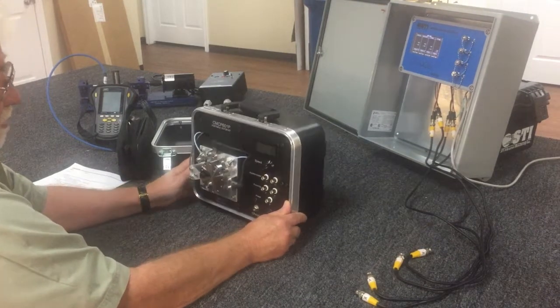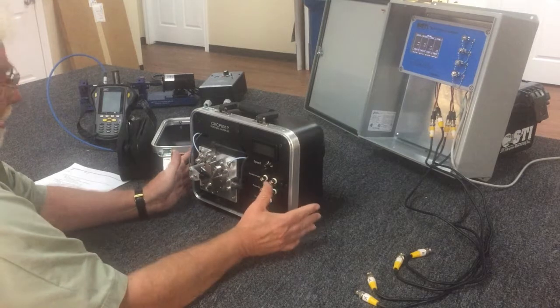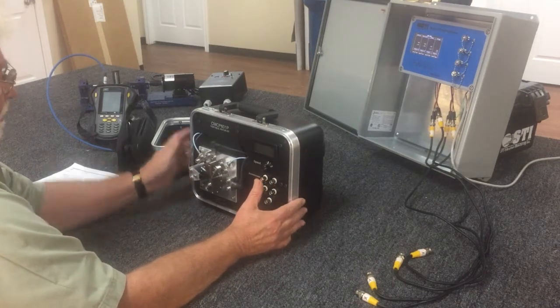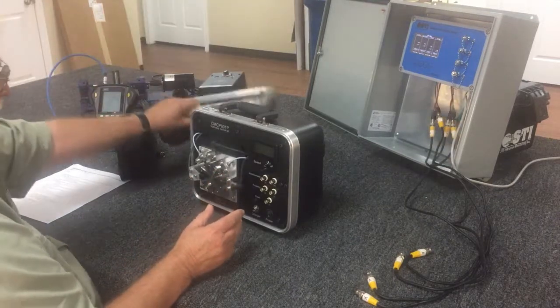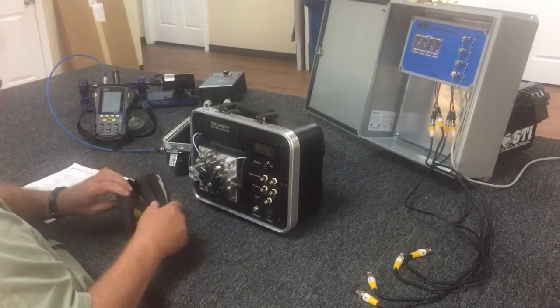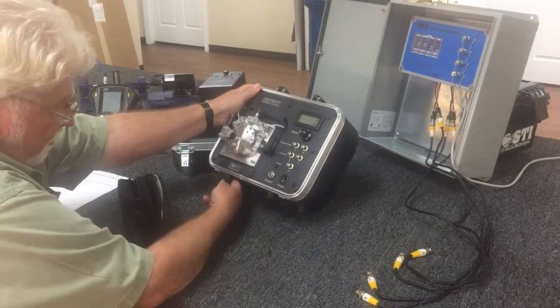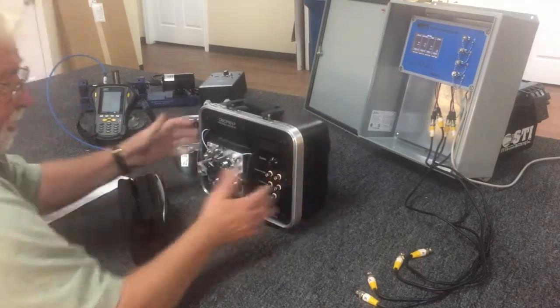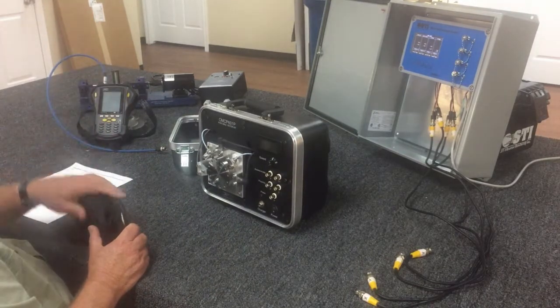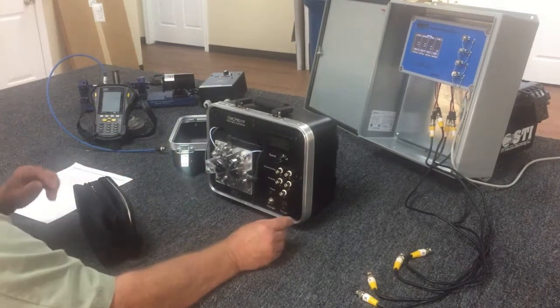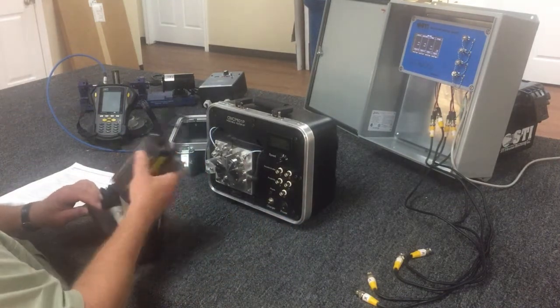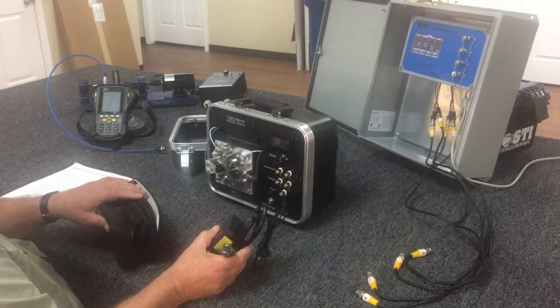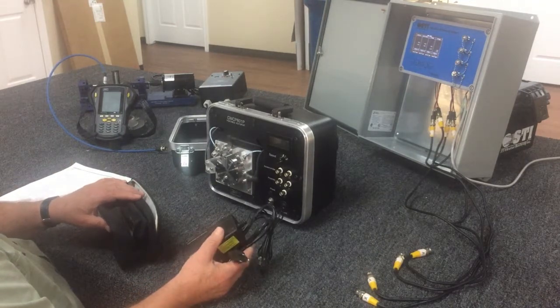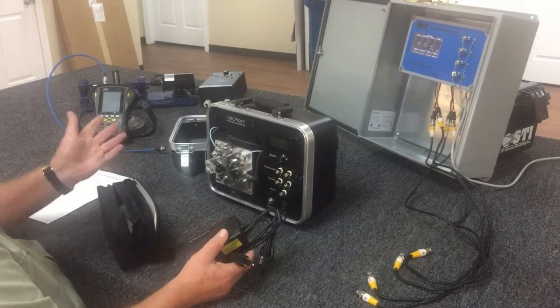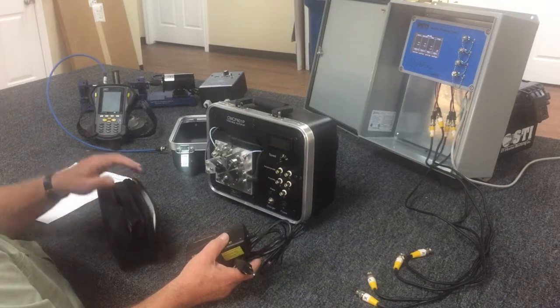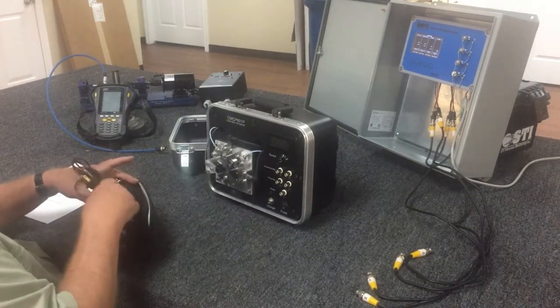Okay. What you get is the CMCP601P and a 12 by 12 by 10 inch deep carrying case, which has a lid. You get rubber feet on the bottom to make it easy to sit on a tabletop or a conference room without scratching, to do your demonstration of an analyzer or monitoring system, or to teach balancing. You get a kit which includes a smart charger for the lithium-ion battery. It's internal to it. It's a 1.2 amp charger, 2.6 amp battery, so call it 4 hours and you should be fully charged back up again. But once again, you're going to get 8 to 10 hours of runtime out of it.